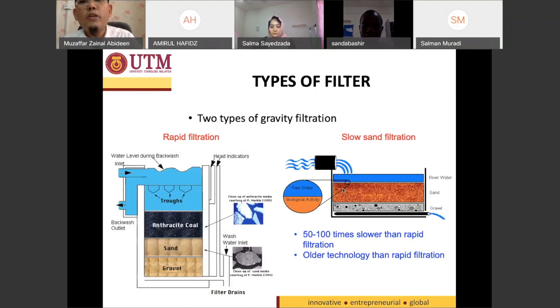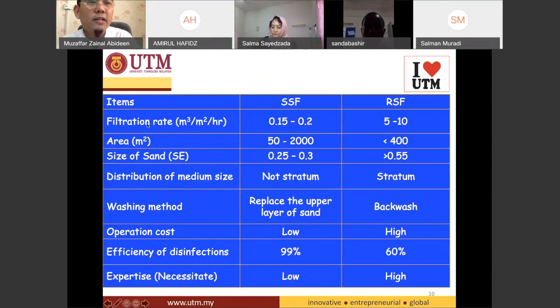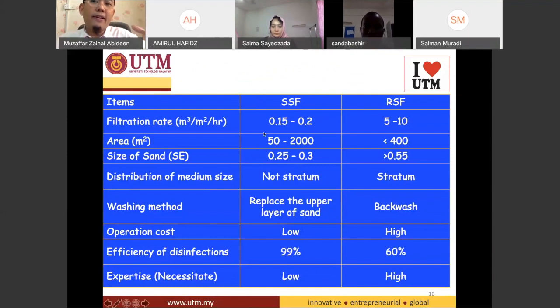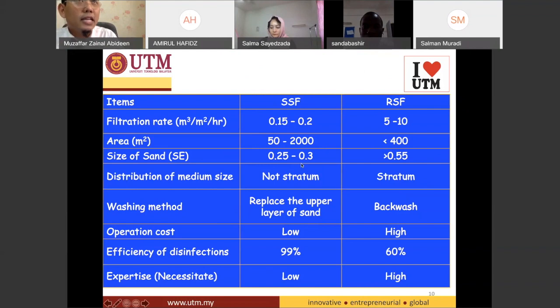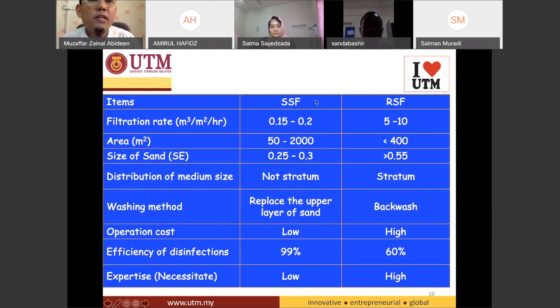What are the differences between the slow sand filter and the rapid sand filter? When you have the slow sand filter, the filtration rate will be slower than the rapid one. The slow sand filter also requires a greater area compared to the rapid sand filter. That's why the rapid sand filter is more common in Malaysia — the cost of land is very expensive, so people opt for the rapid sand filter.